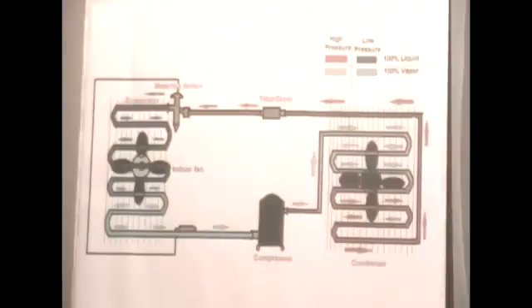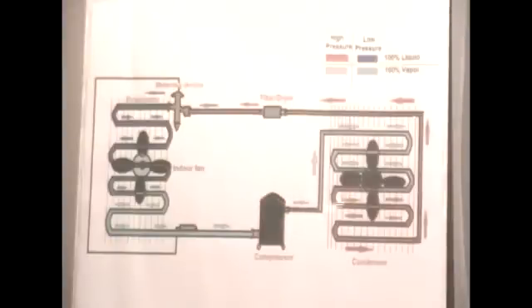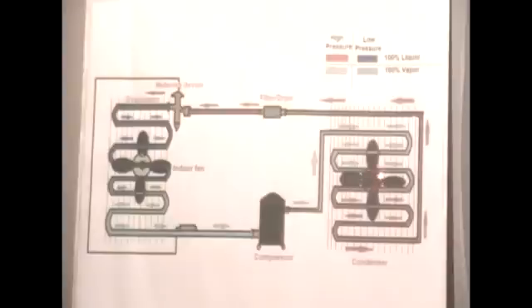Let's first look at the compressor. The job of the compressor is to compress your refrigerant from low pressure at the inlet from your suction line, and compress it to high pressure when it comes out to the discharge line. It then goes into your condenser. The condenser's job is to condense the refrigerant by releasing heat via the condenser fan motor. It changes the state from high pressure, high temperature vapor to high pressure, high temperature 100% liquid.